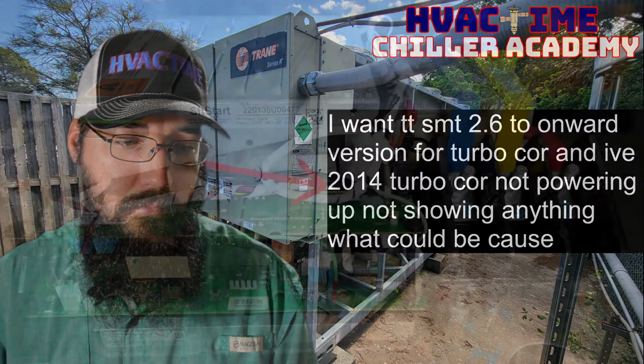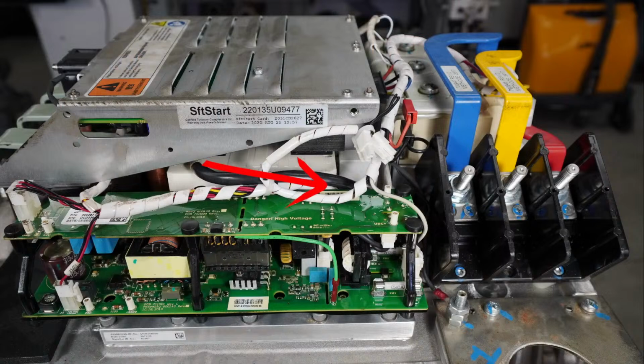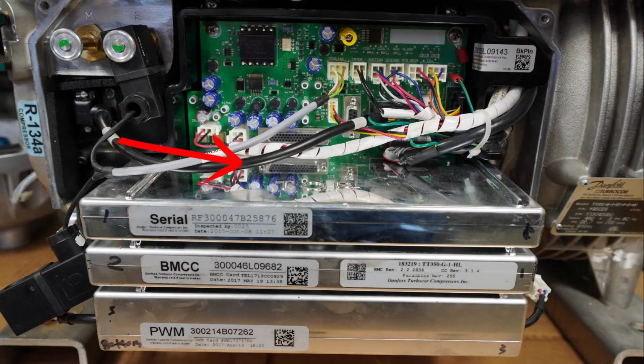First, so this is the top of a TT, should be a 350 series if memory serves. So depending on your particular one, you could see a couple of different things up here. One, the smaller ones don't have a fuse block assembly here. The larger ones do. So if you're not seeing anything boot up, specifically what that could mean is either on your backplane board or your I/O board, which I don't have a quick picture of, but that's going to be down in the control panel close to the system controls.